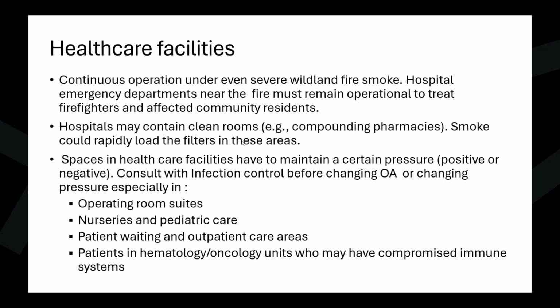Now, to sum this up, for healthcare facilities, why are we worrying so much about wildfire smoke? The reason is that it's very difficult to evacuate healthcare, especially an acute care hospital. This is why it has to continue operating, even if the wildfire smoke becomes intense. And even the ED department has to continue operating to provide healthcare to the firefighters and the affected communities. Hospitals are also among the facilities that will have terminal filters like your HEPA filters in your compounding pharmacies or in your ORs. And these could load with wildfire smoke, even if your house system has MERV 13.